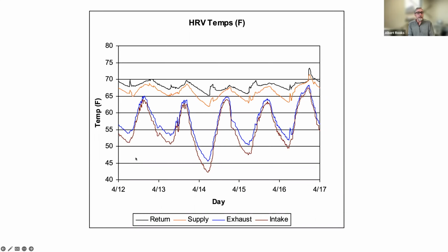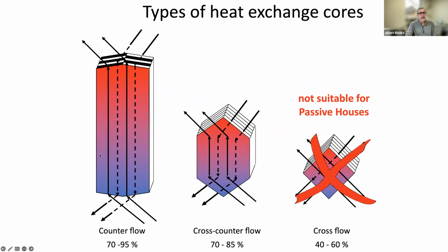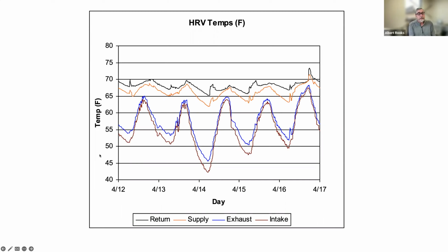So the blue line is the exhaust air that's leaving the building, right? So we're pulling from the kitchen and bath, we're doing the heat recovery. And then after doing the heat recovery, we're sending that used air outside the building and saying bye-bye. And at the same time, we're pulling in fresh air from outside. And so that very bottom line is the fresh air coming in, and that's its temperature scale. And so you can see that maybe one thing we can't see, I don't think I've got notes on, no annotation. So this is actually April in 2013 or 14, I think.